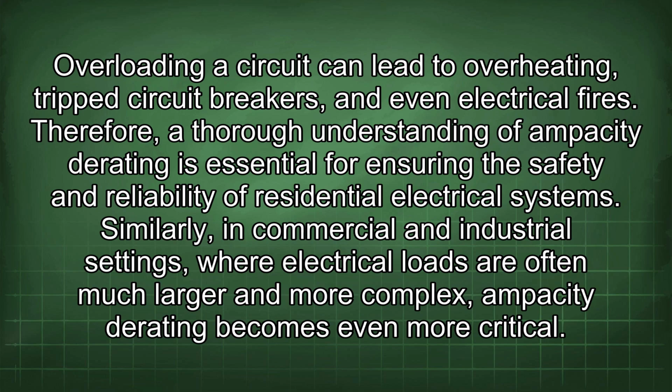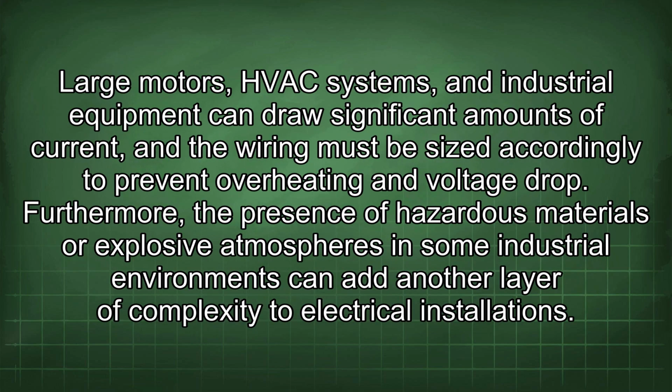Similarly, in commercial and industrial settings, where electrical loads are often much larger and more complex, ampacity derating becomes even more critical. Large motors, HVAC systems, and industrial equipment can draw significant amounts of current, and the wiring must be sized accordingly to prevent overheating and voltage drop.